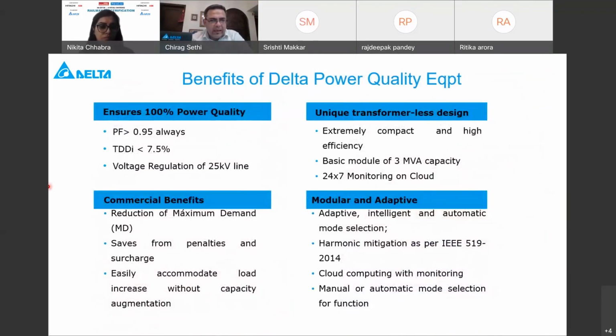This brings me to my last slide, just to summarize the benefits of our dynamic power quality solution. It addresses the requirement of power factor, harmonics, as well as voltage regulation. Commercial benefits to customers include reduction in maximum demand, saving from penalties and surcharges, enhancement of load. It is a unique transformerless design, whereby the footprint, the space requirement, is pretty low. Since there is no transformer, there are no associated copper losses. So it is high in efficiency.